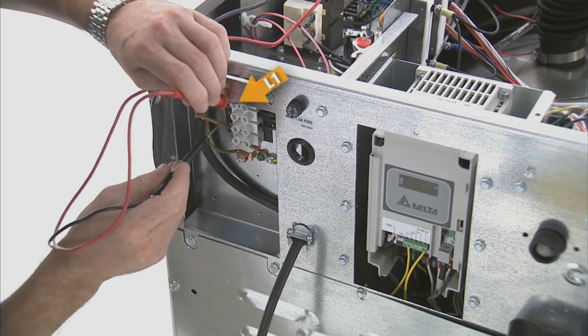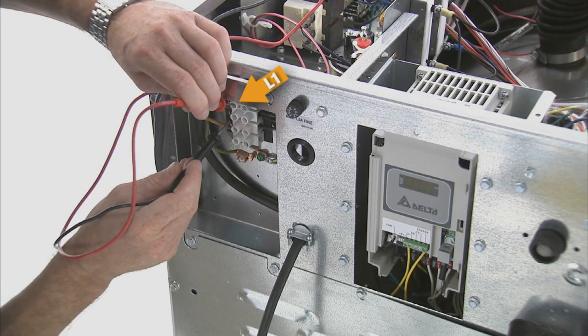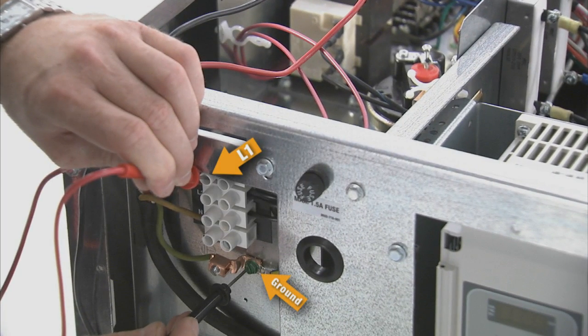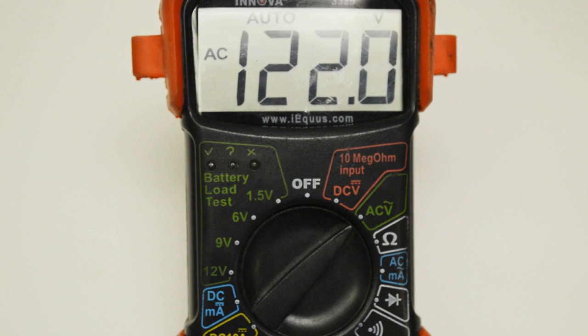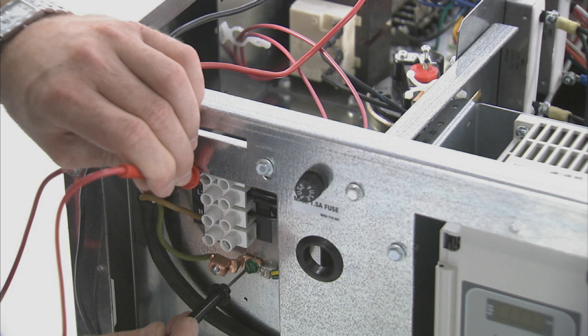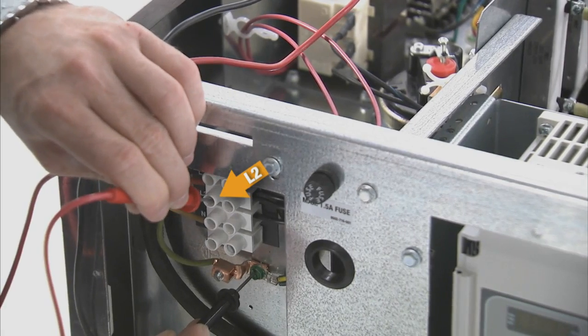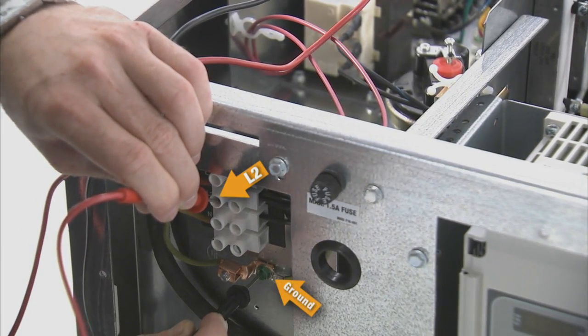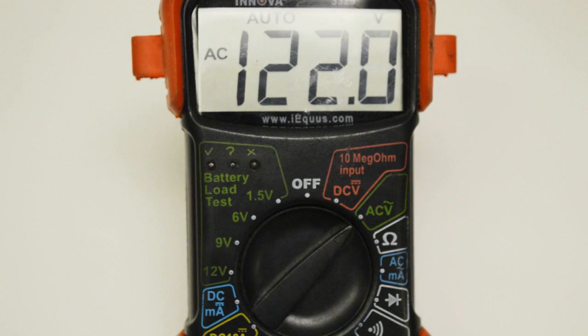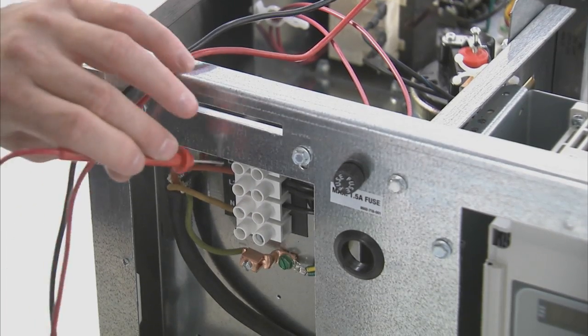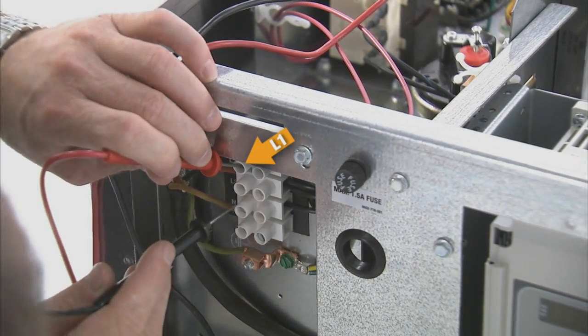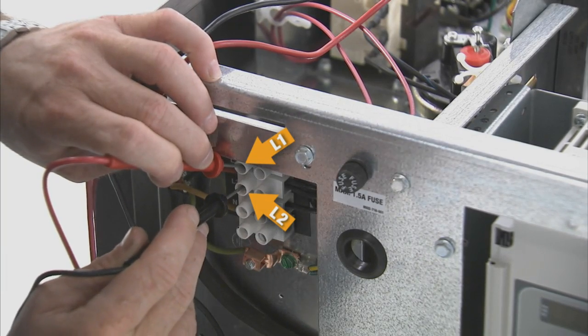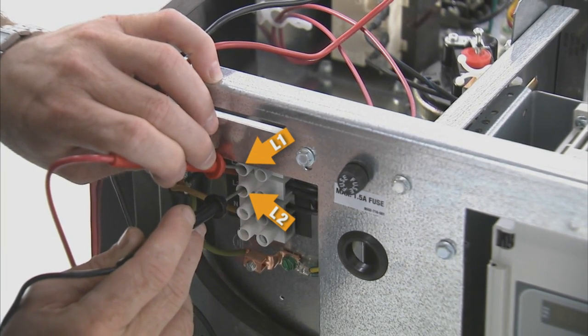put the red lead on the L1 terminal and the black lead to the ground on the terminal block. Next, put the red lead on the L2 terminal and the black lead to the ground on the terminal block. If the voltage is not the same on both L1 and L2, consult a certified electrician to correct the issue. The next step is to place the red lead of the voltage meter on L1 and the black lead on L2 to check for total incoming voltage.